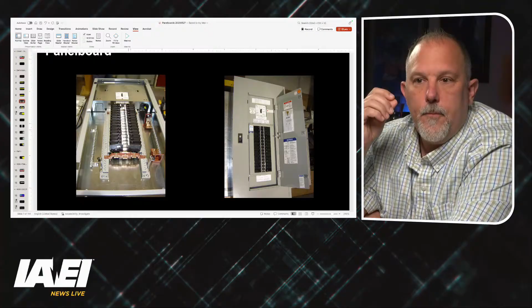The interior of this piece of equipment, and what I'm showing over here is actually a Canadian panel. So all of the Canucks out there, this is my line side barrier. This is a Canadian panel board that has the complete upper portion blocked off, based upon the rules up in Canada, because you're not allowed to bring any conductors other than the service conductors into that area.